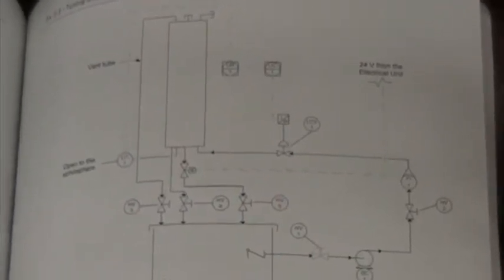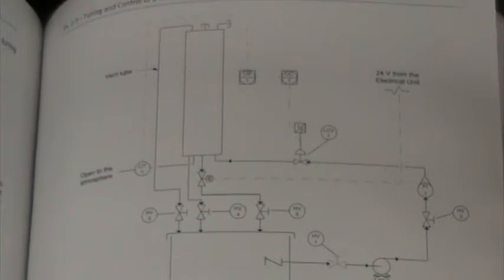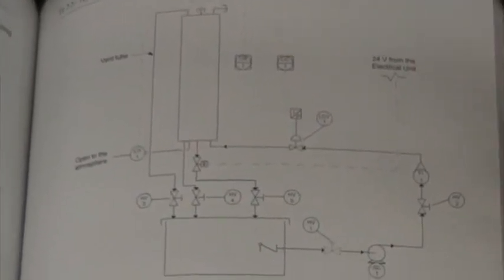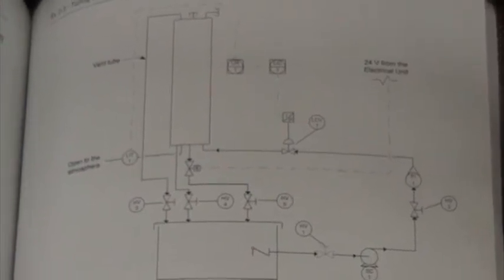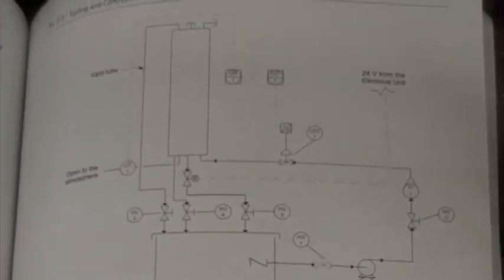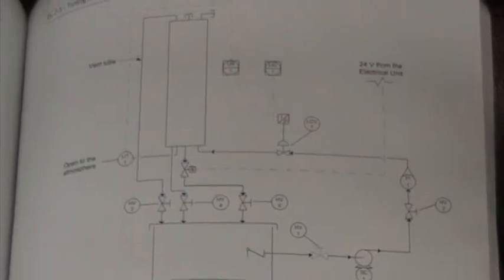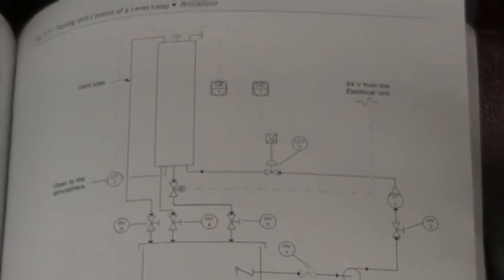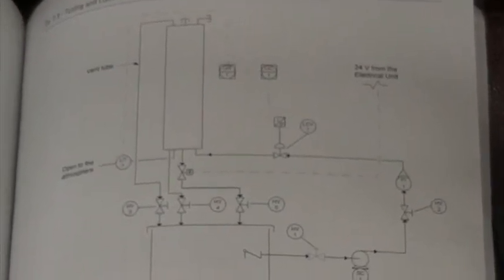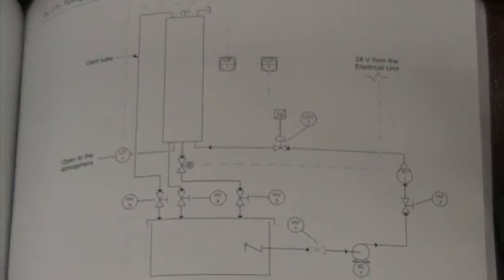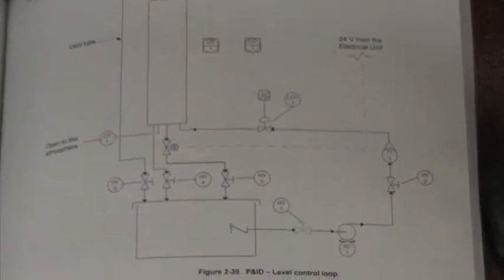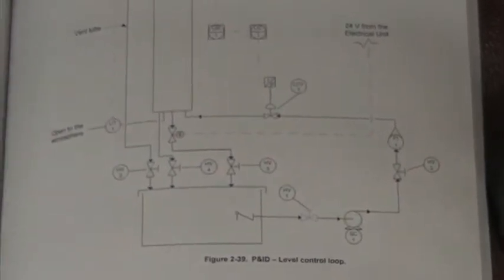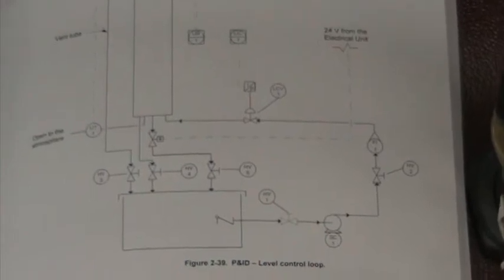I have left hand valve 4 slightly open to allow the water to drain into the tank at the bottom. Otherwise, I will not get the type of control that I want. If the valve is closed and the water is below the set point, once the water reaches the set point, it will simply close the valve, and that's not the type of control that I want.